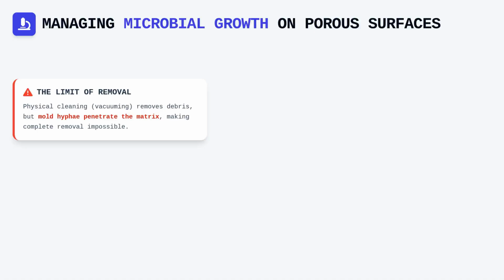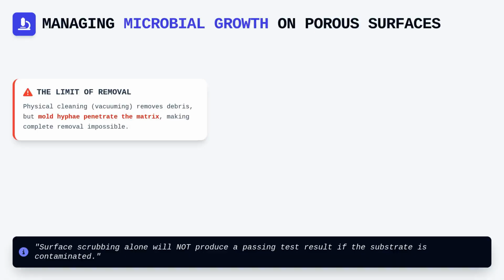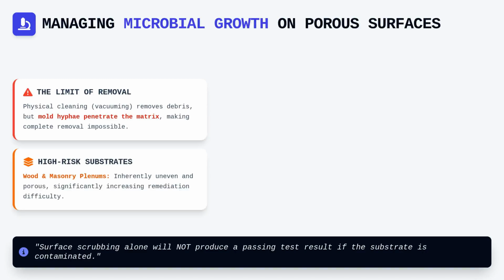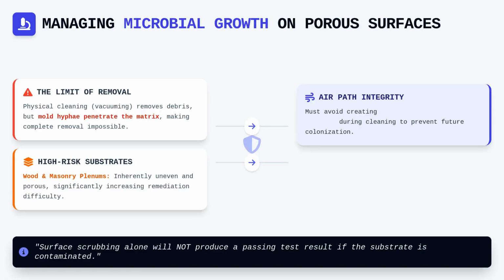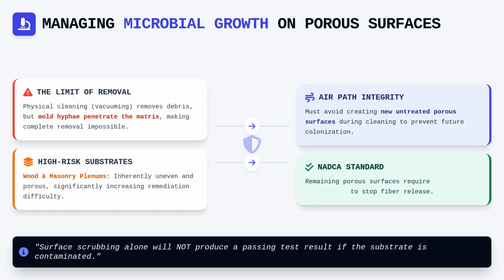If you identify significant microbial colonization, you cannot simply scrub the surface and expect a passing test result, because the substrate itself is contaminated. In scenarios involving wood or masonry plenums, the difficulty increases because these surfaces are inherently uneven and porous by design. We must ensure that our cleaning process maintains the integrity of the air path. Otherwise, we risk creating new, untreated porous surfaces that can foster future growth. If a porous surface must remain in service after cleaning, NADCA standards may necessitate the application of an encapsulant or sealant to prevent fiber release and further contamination.